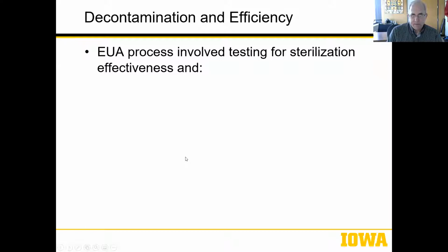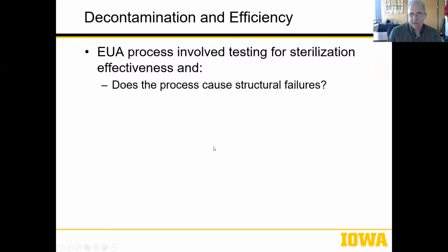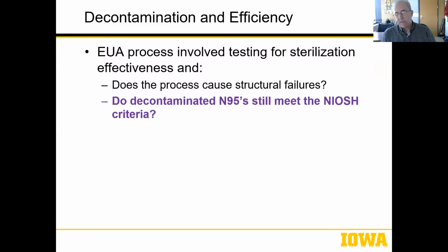Now in this process, obviously they had to prove that the sterilization was effective, but what about the device itself? Does it cause structural failures? Do the straps still work, or do they get corroded? Can you actually reuse it? Does it help have a good fit? Does it keep that seal around your face? And does it still meet the NIOSH criteria? Is it still an N95 as I've described to you?